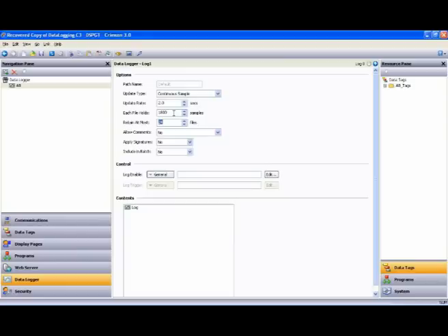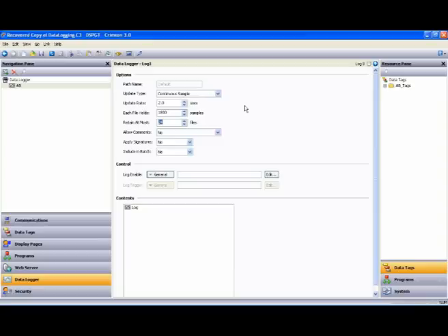Now, since the Data Logger operates on a first-in, first-out basis, when the Data Logger puts the specified number of samples in the last file, it automatically starts overwriting the samples in the first file, so this example always shows the last 24 hours' worth of data.